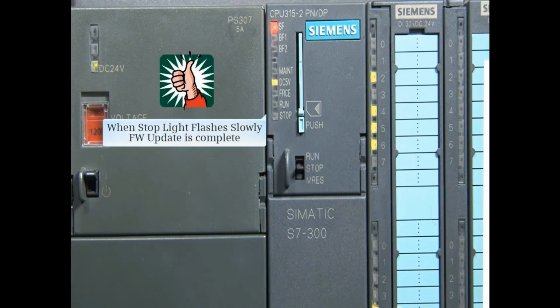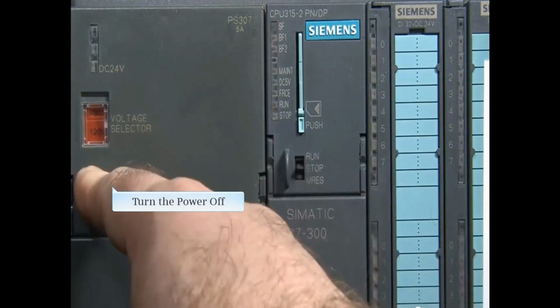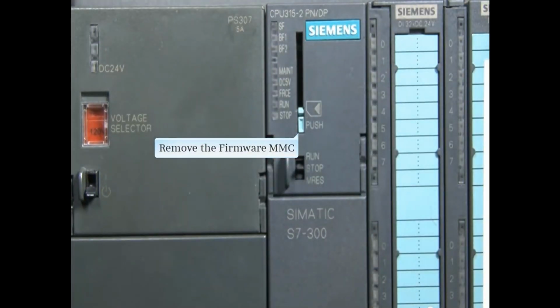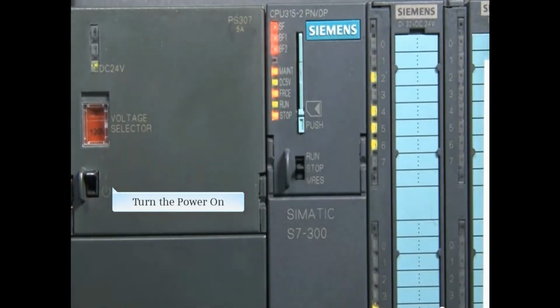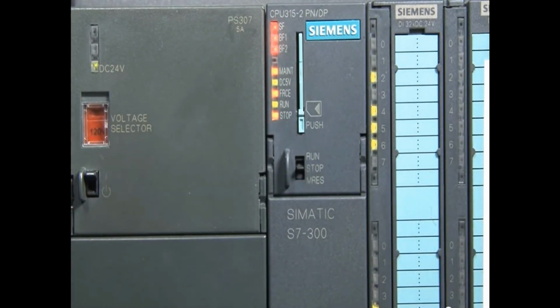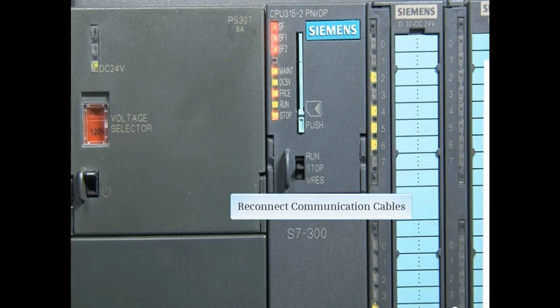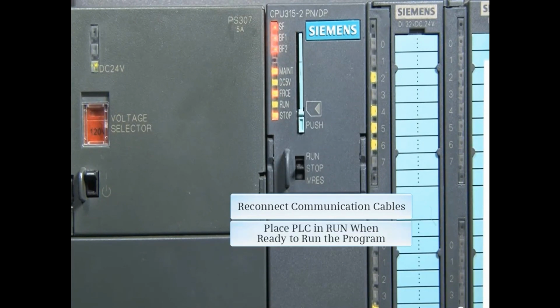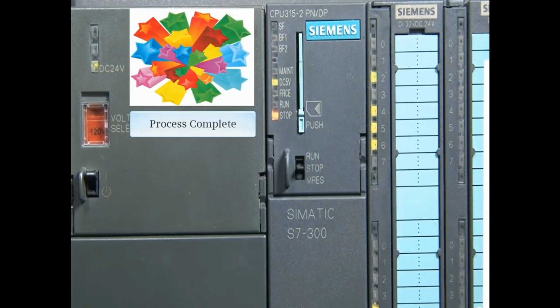When the stoplight flashes slowly, the firmware update is complete. Turn the power off and remove the firmware MMC. Replace the project MMC and turn the power back on. Reconnect the communication cables and place the PLC in run when ready to run the program. The process is complete and successful.